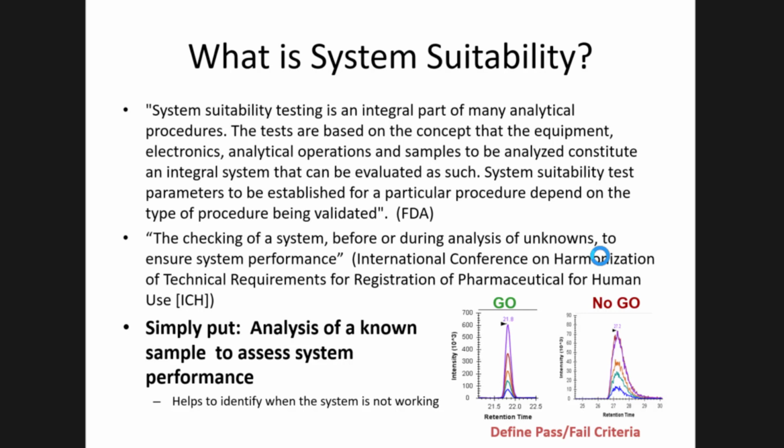And so you can see here, this peak width is less than 30 seconds, and this one is like 2 minutes. So it's always a good idea to help you have confidence in your system performance and the data you're producing with it to do system evaluations. Some people use QC as a term for this. I use system suitability because it's evaluating the whole system and not just aspects of a workflow, which is what I would use QC for.